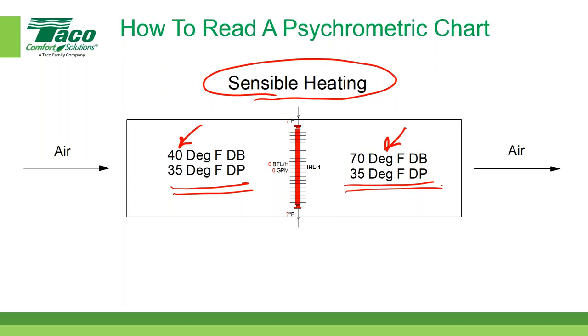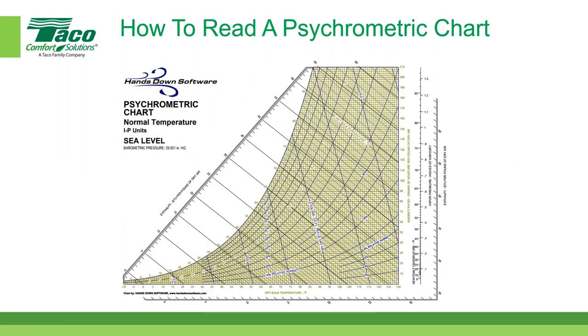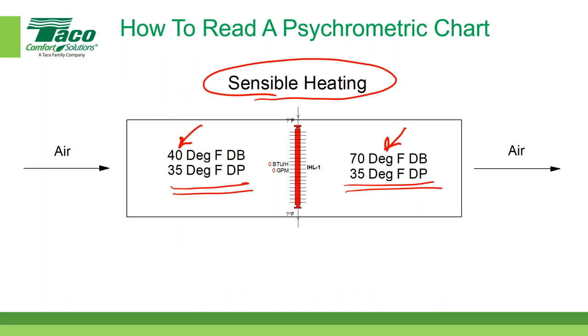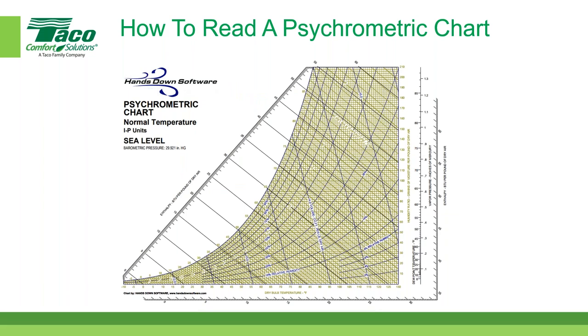So we're going to plot this out on our psychrometric chart. Bear with me, these lines aren't the most accurate in the world, but you can get the general idea of what we're talking about. We said we wanted to go from 40 to 70, at a 35 degree dew point temperature. So I'm going to go over here to the dew point temperature line, which is roughly 35 degrees. I'm going to start from 40 degrees Fahrenheit, which is roughly here. And what did we say, Brett? 70 degrees Fahrenheit? You did. So I'm going to start over here and draw a line. Oops. Try this again. There it is. So that's called sensible heating.